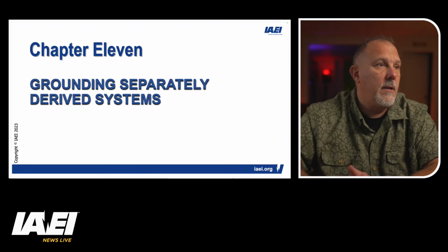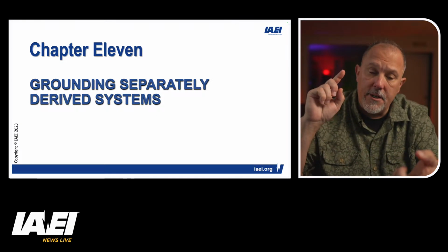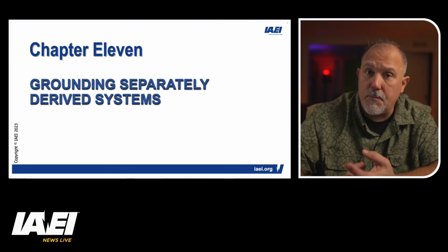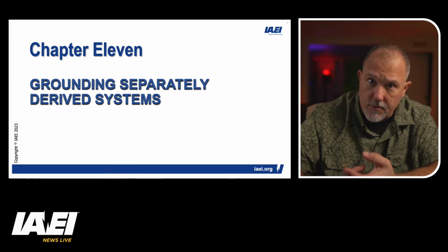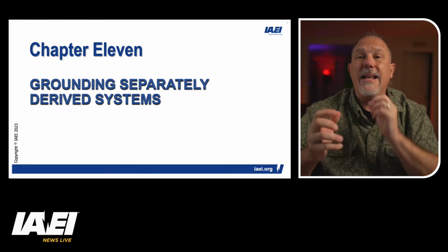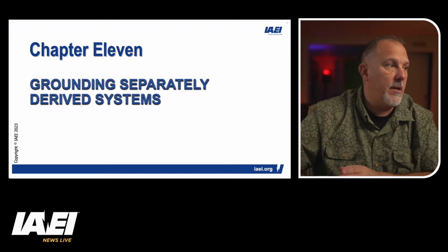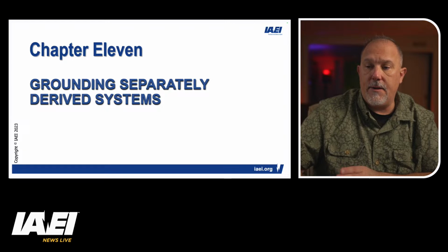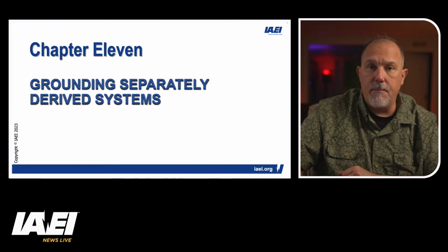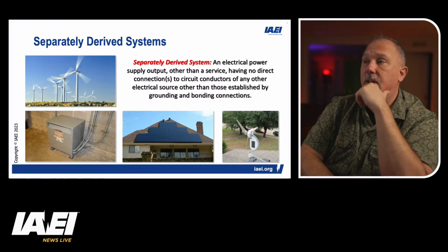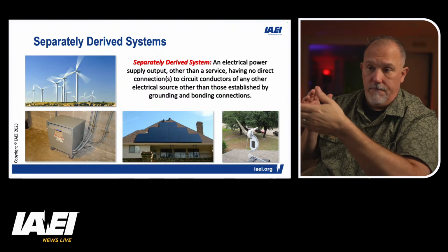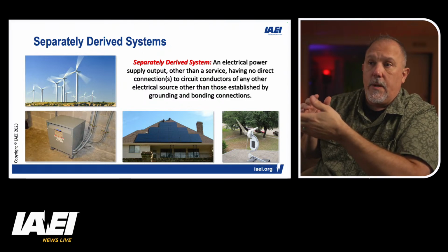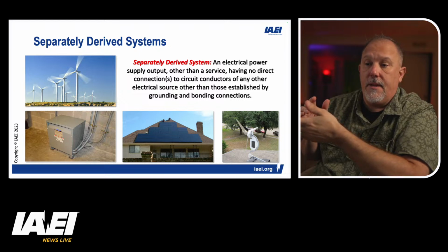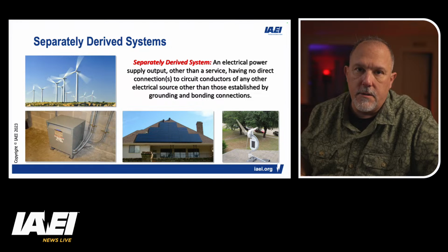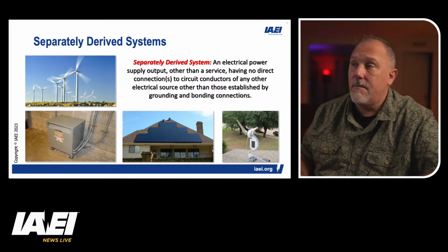And then you're going to have to protect. You protect the conductors from the separately derived system. You protect the source of the separately derived system, whether it be a transformer, a generator, etc. And then it's at that separately derived system that we establish our grounding and bonding. Now, some good examples of separately derived systems. There's your transformer. Gotta love the transformer. I mean, there's a workhorse right there. If that's not a fundamental piece of equipment that is pretty much found in every power distribution system that is an AC system, transformers are it. I mean, conductors, but transformers, come on, right? Very common piece of equipment.